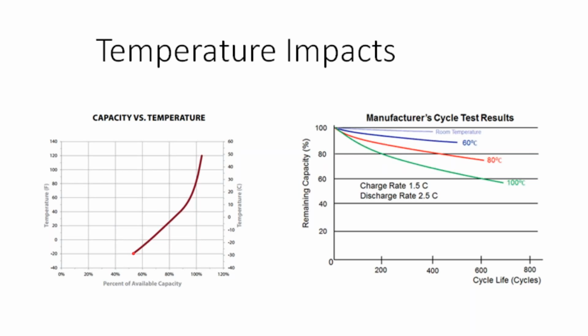Well, we've seen there's some winter conditions where we might be going all the way down to the bottom range of your batteries. So if we want our batteries to be in a cold environment, we have to prevent them from freezing. We'll get longer life out of our system. We'll get more efficiency out of our system if they're in air conditioning. And so that kind of begs for the whole system, the batteries and the inverters, to be in a temperature controlled environment.